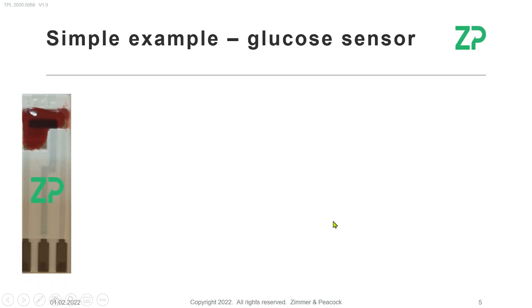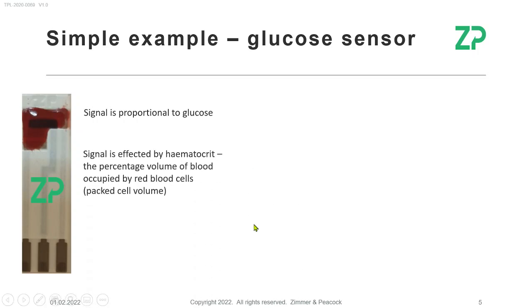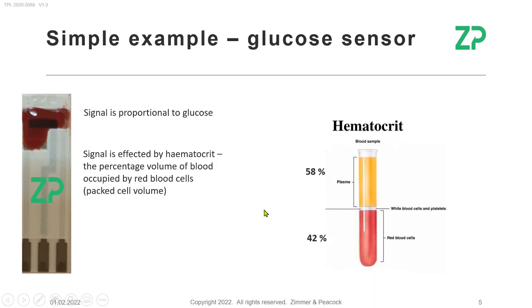So if we take a simple case like a glucose sensor, here we have a glucose sensor with a drop of blood in it. So the signal there is proportional to glucose. But also, the signal is affected by the hematocrit. And now the hematocrit is really the volume that's taken up by red blood cells. So if we just illustrate that a bit more, if you centrifuge whole blood, you're going to find a dark red phase at the bottom of the tube and a clearer yellowy phase at the top of the tube. And at the top we basically have plasma, and at the bottom we have red blood cells.